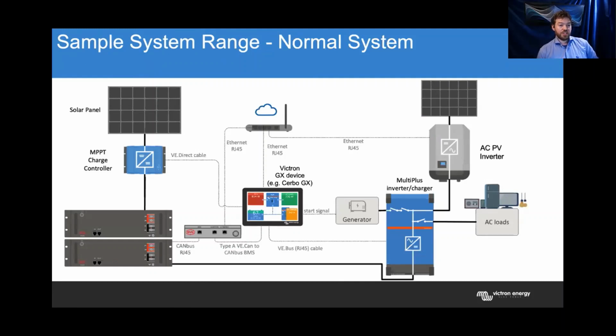In this case, we've got a generator integrated into the system as well, using an auto start and a connection to VRM and an AC PV inverter. In an off-grid system, the Venus controls the charging power of that AC PV inverter using the commands from the BYD BMU.